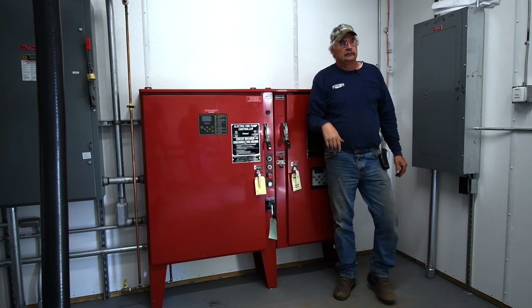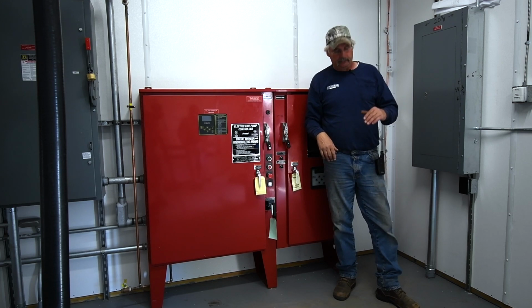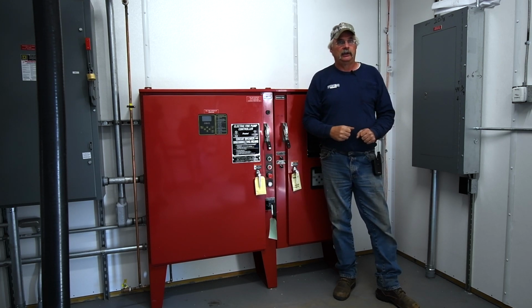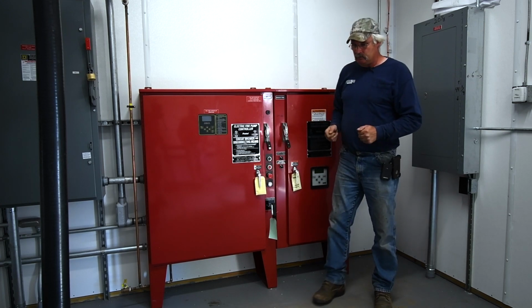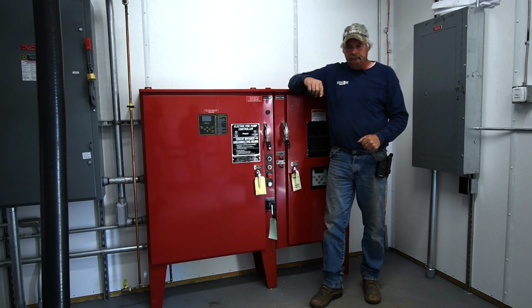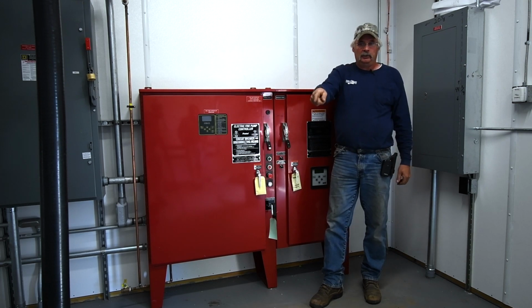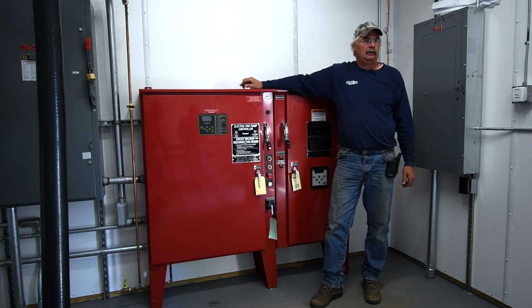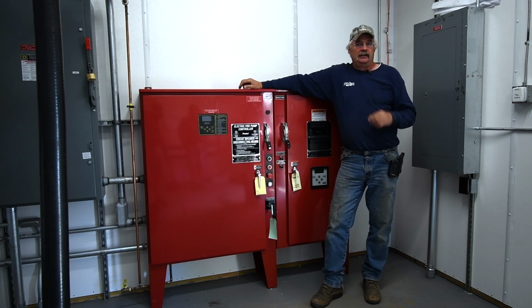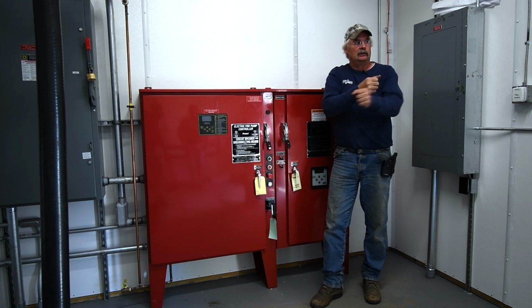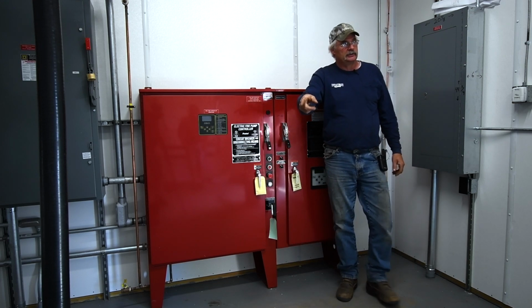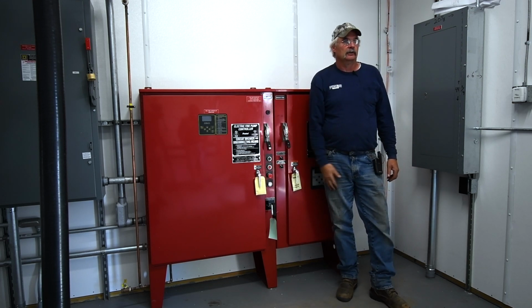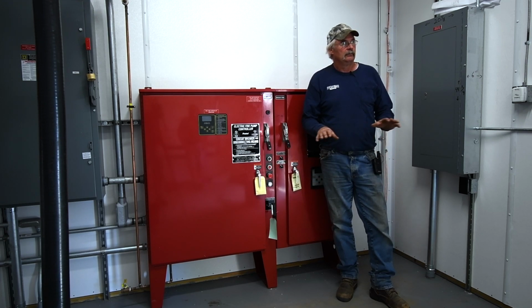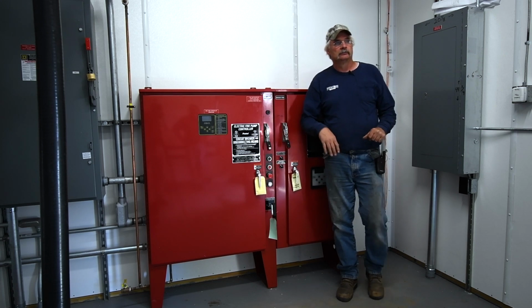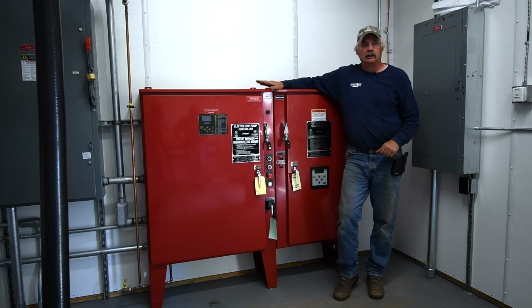And what they mean by phase reversal is, if a tree goes down on your power line and rips your cables out of your wall, the power company comes back out and puts your leads back in. If they mix them up, the pump will still run, but the panel will pick it up immediately and say phase reversal. At that time, the power company switches the leads, checks it out, makes sure the rotation's correct on the fire pump, and you're good to go. So they're trying to take everything away from worry, so it's trouble-free. And that's why you have a dual disconnect cabinet.